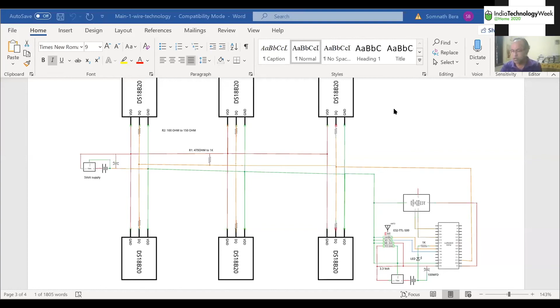This is the typical microprocessor, this is the display unit, and this is the typical radio uploader. It gets data from all those 50 to 100 to 500 temperature sensors. When you call them by address, the temperature comes depending on the resolution you have set. It comes to the microprocessor, which puts it in a CSV file and uploads it. This uploaded signal is received by the receiver, which is another computer or laptop with a processing output, and there it is monitored cell-wise.